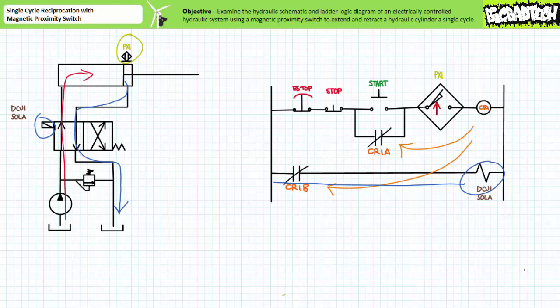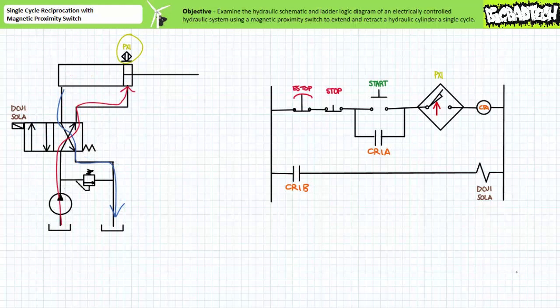Contact PX1 opens, which breaks the current path energizing the coil of control relay CR1. All contacts associated with CR1 return to their deactivated state. CR1A opens and removes the holding circuit; CR1B opens and DCV1 Sol A is de-energized. On the hydraulic side the de-energized solenoid returns the spool to the cross-connect position. Pressurized flow enters the rod end, the cap end is connected to tank, and the cylinder retracts.